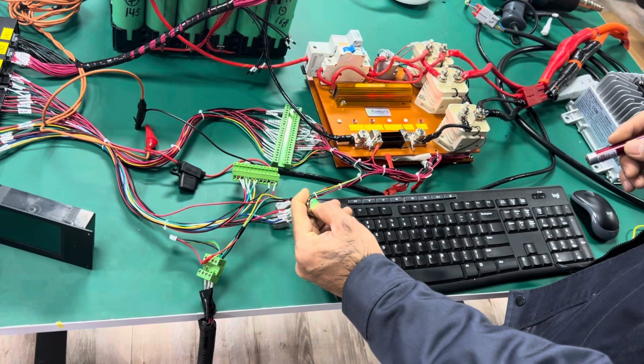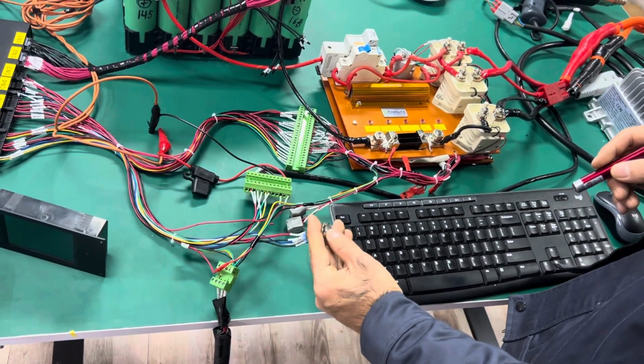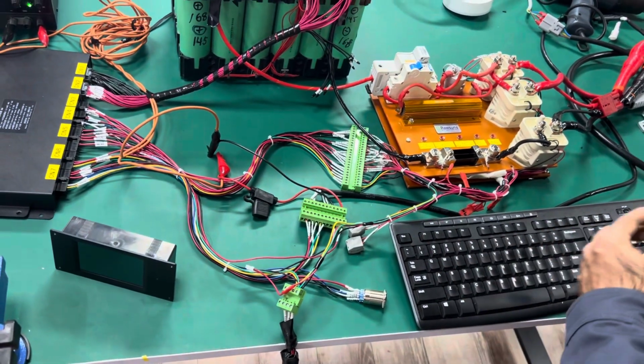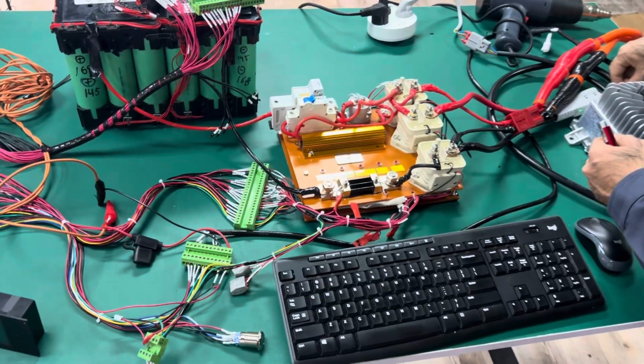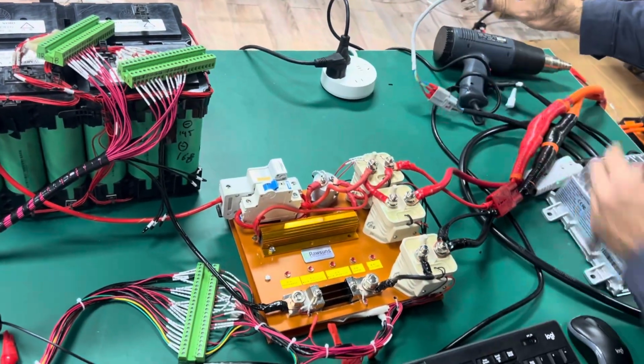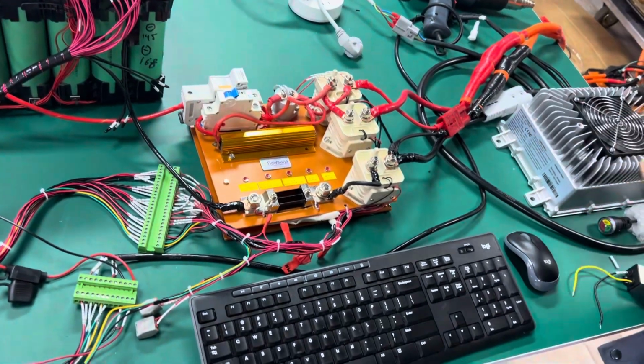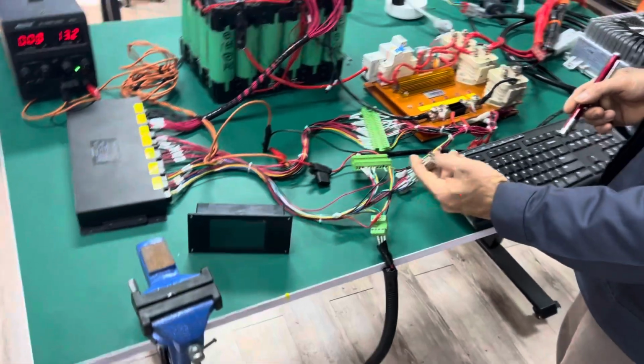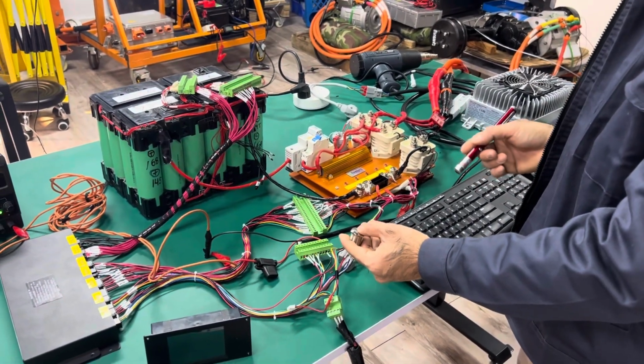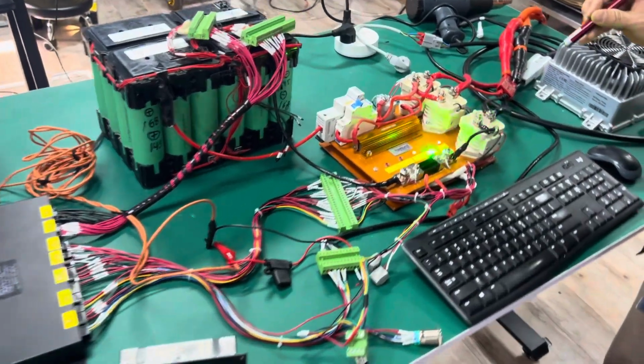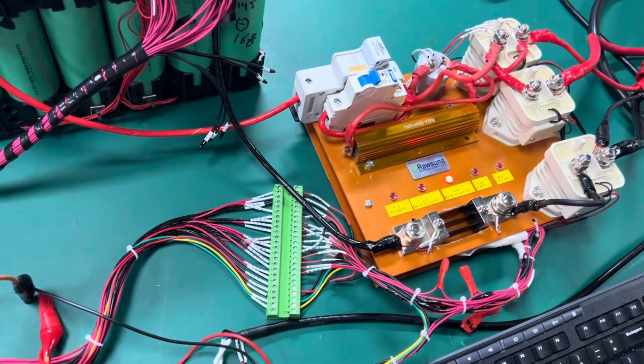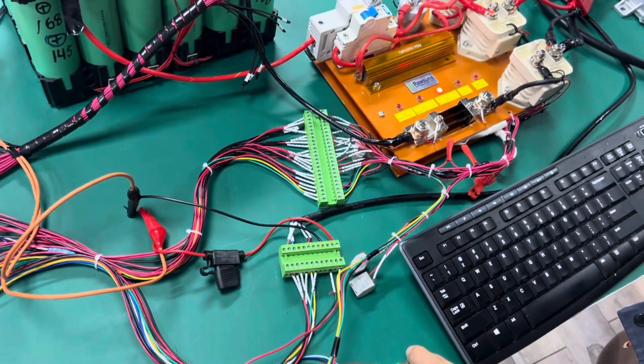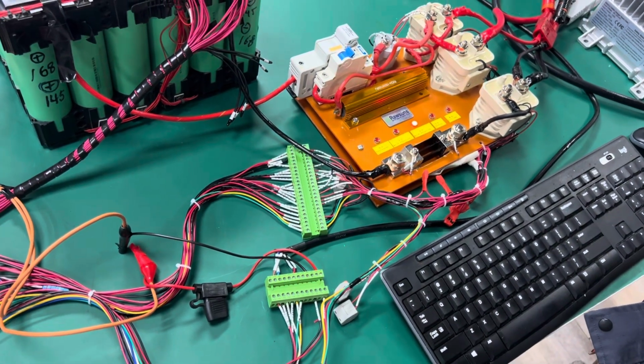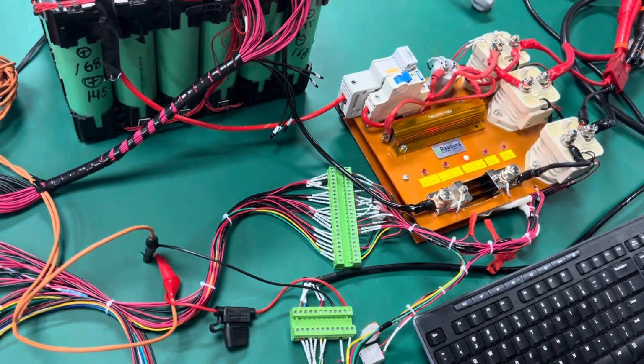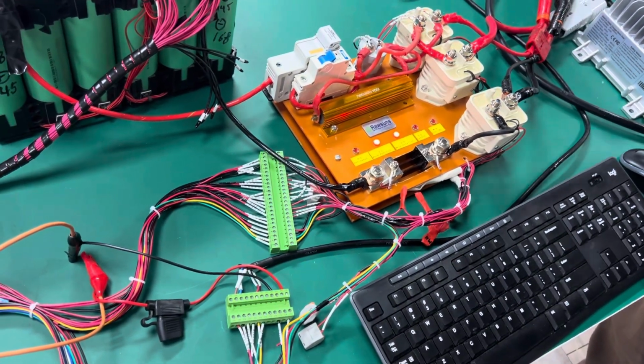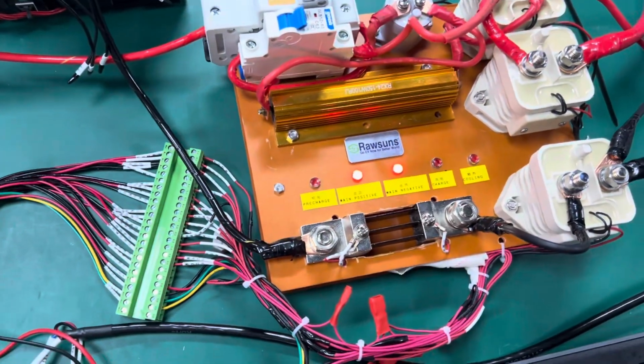We can press this button for more than 3 seconds, and the system will be off. Now I disconnect the charger. This is the charger power. I disconnect the charger power, and then now I start the battery again. Press the button for a short time. We can see now the main negative relay is on, and the main positive relay is not closed. So let me check. Maybe the... now it's on. It's on. Maybe just now the charger was still connected.